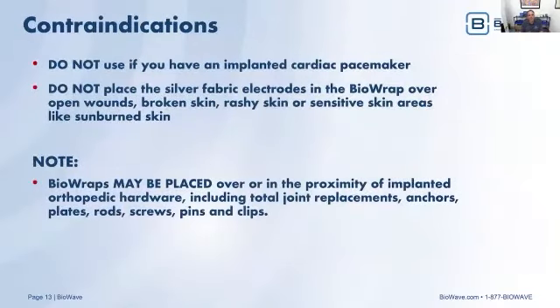The contraindications for this device are you cannot use it if you have an implanted cardiac pacemaker. There's no negative data, and even though the treatment is located very far away from where the pacemaker is located, the FDA requires us to contraindicate it for those types of patients. The silver fabric electrodes must be placed over intact skin. So you cannot use this electrode compression garment if the silver fabric is going to be over open wounds, broken skin, very rashy skin, or sensitive skin areas like sunburned skin.